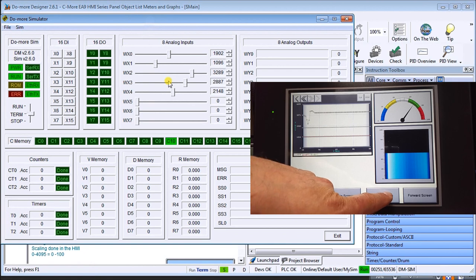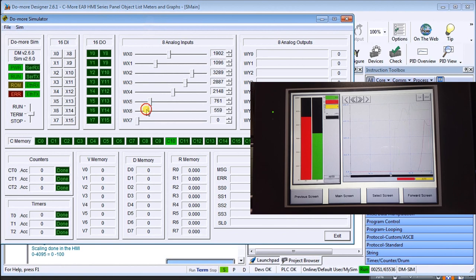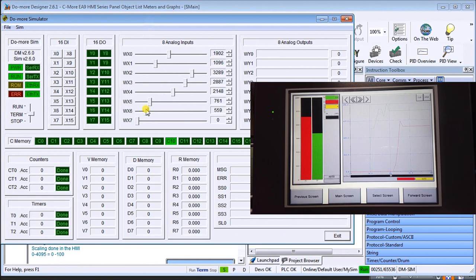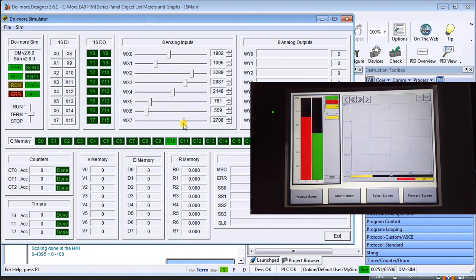Let's look at our PID face plates. The last three values are set value, present value, and output. Moving the sliders, we can see the present value change. The set value can be changed and it goes up in the bar graph as well. On the chart, you can see it charting exactly what happened over the last little while. The output slider changes the output value up and down. Using the buttons at the top, we can hit stop, clear the chart, start again, and monitor those values as we go up and down.